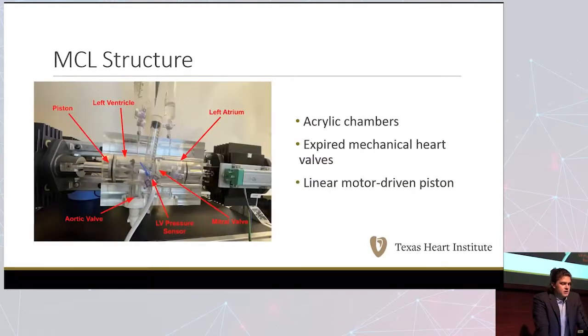So the MCL consists of acrylic chambers that represent the left atrium and the left ventricle. And mechanical heart valves for clinical use are used to simulate the aortic and mitral valves in their respective locations. Syringes are attached to the rigid chambers to add some compliance. And a linear motor driven piston is what creates pulsatile flow in the system.